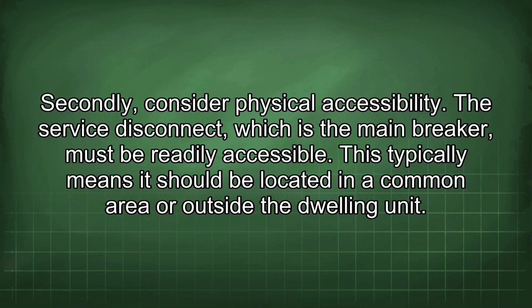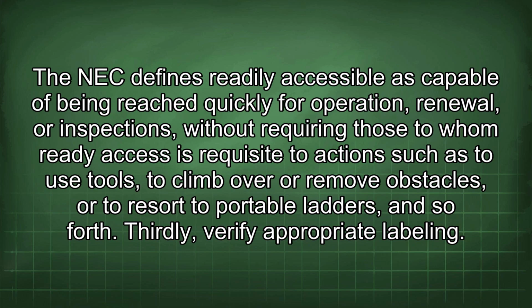Secondly, consider physical accessibility. The service disconnect, which is the main breaker, must be readily accessible. This typically means it should be located in a common area or outside the dwelling unit. The NEC defines readily accessible as capable of being reached quickly for operation, renewal, or inspections, without requiring those to whom ready access is requisite to take actions such as to use tools, to climb over or remove obstacles, or to resort to portable ladders, and so forth.